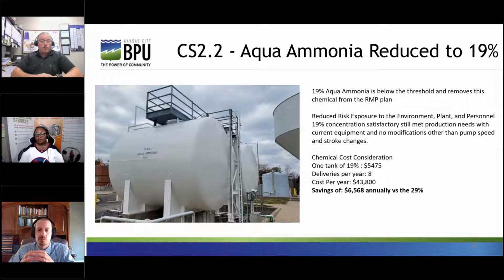As asset management is a multifunctional approach, this change effort took internal engineering and operations to come up with a good solution. Operations and engineering found that 19% aqua ammonia could be used with only metering pump stroke and speed adjustments, which were well within each pump's capacity and capability. We still treat the aqua ammonia system as though it's under the risk management plan and with respect, and it saves us around $7,000 a year in chemical costs, which is a nice bonus for the change.